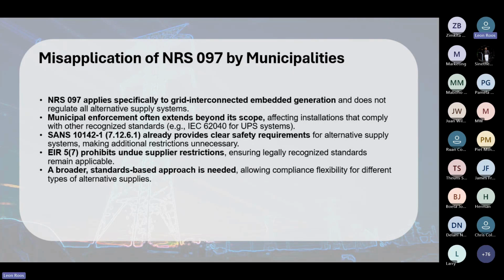SANS 10142 does make provision for other types of installations, and under 7.12.6.1, if it is a parallel system with the grid as an alternative supply, there are additional restrictions, and these additional restrictions are unnecessarily set out by the municipalities.